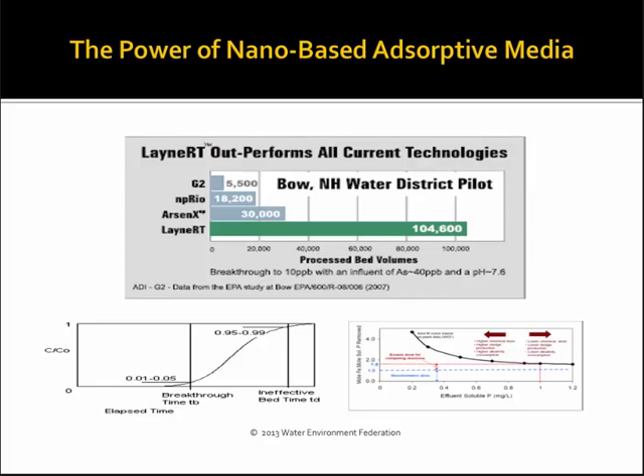In water treatment chemical removal, the metal salt to P ratio stoichiometrically is about 1.8 to 1 to achieve 1 mg/L discharge of P. But to meet restrictive standards like Chesapeake Bay or Snake River, Idaho — down to 0.2 or lower — the stoichiometry gets out of hand, over 4:1, and chemical costs go through the roof. Inversely with ion exchange chemistry, you start with a fresh bed, come out near non-detect, and go through a typical ion exchange breakthrough curve. If this line is your discharge limit, you change vessels comfortably below it. In all that territory below your permit level, you get nutrient trading credit right off the bat.